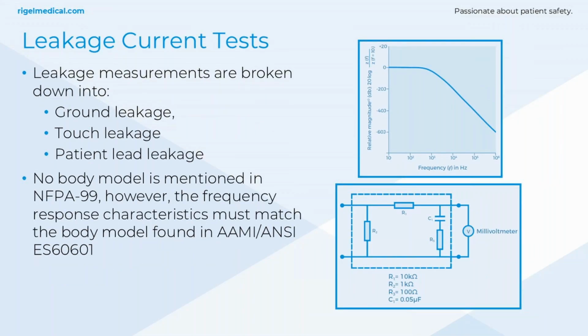So leakage measurements can be broken down into ground, touch, and patient leakage. The terminologies can sometimes change, and they may look different on the safety analyzer that you're using, and people call them by different things. It might be called touch leakage, enclosure leakage, or chassis leakage, but it's the same measurement that's being made. The circuit is not mentioned in NFPA 99, just that the frequency closely matches that found in 60601. So to measure these currents, you just need a meter whose own frequency response characteristics closely match the body model that you can see on the right-hand side of the slide.